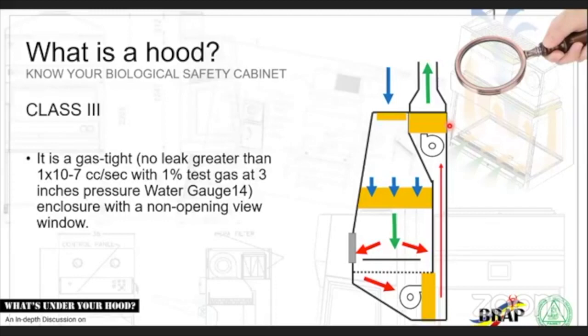Now, class 3. Class 3, this is a very expensive and very hard to maintain system. The entire system is sealed. There's a leak test to ensure that nothing escapes the chamber within this parameter. Right? So this is a 100% exhausted system. Air is filtered in through a pre-filter. Then again, filtered here. This blower at the bottom generates enough force to create a very big vacuum to ensure that air supply is constant in this chamber. So they have a similar system, two grills, one in the front, one in the back. Now this one, all the air is sucked in the bottom, pushed up, and sucked again by another blower.